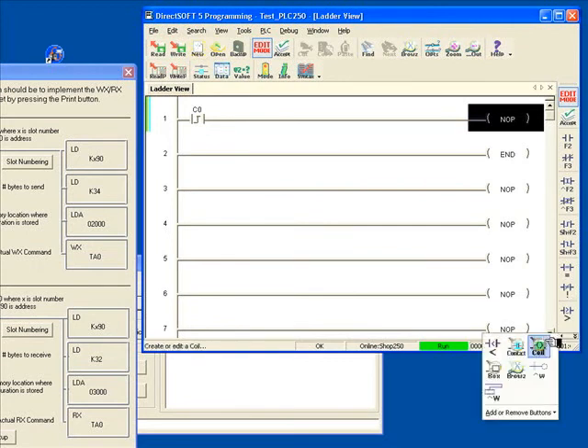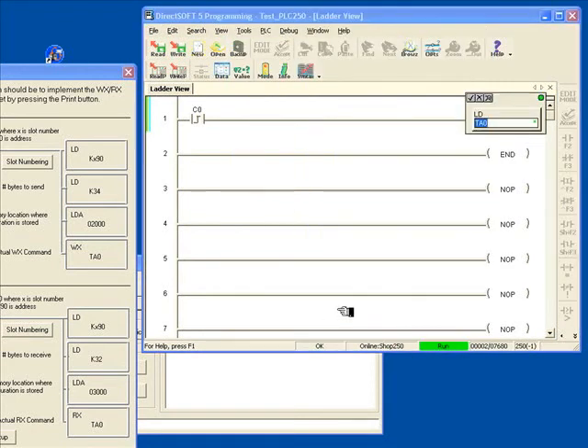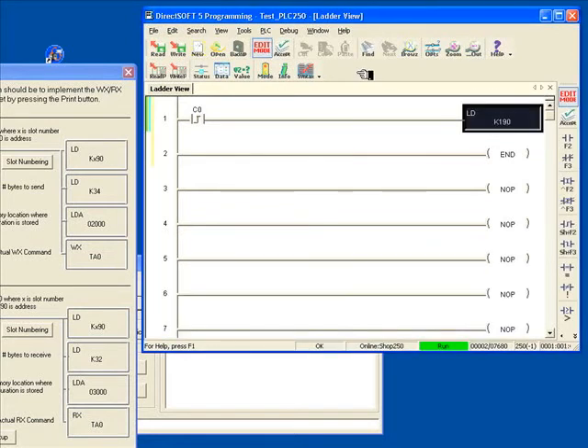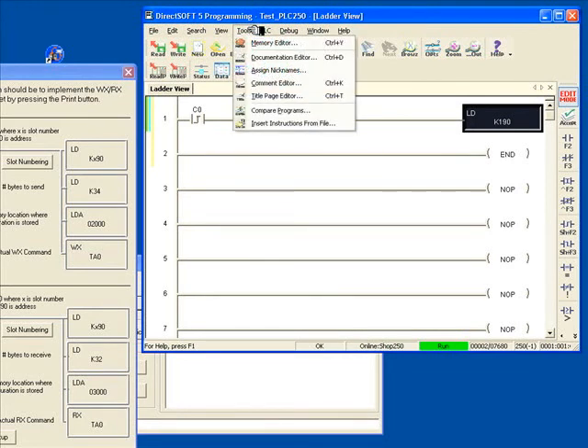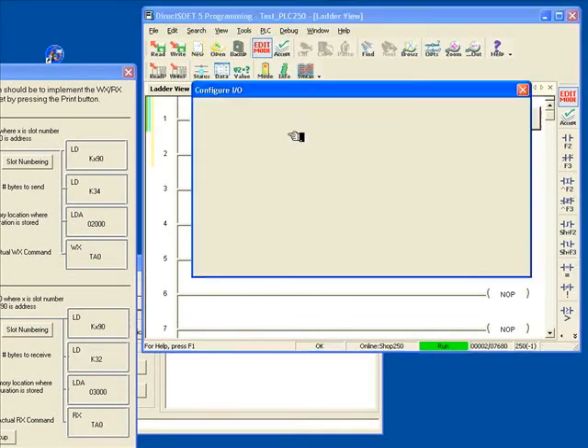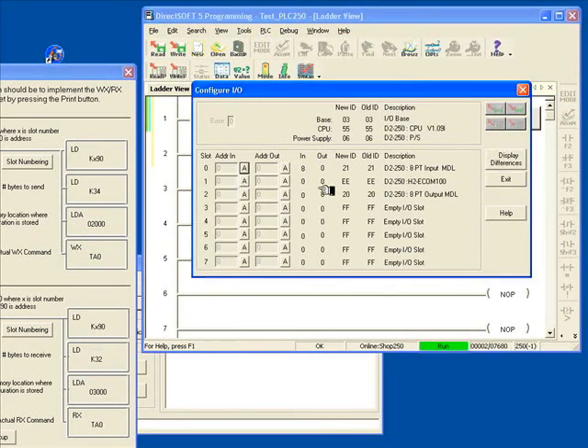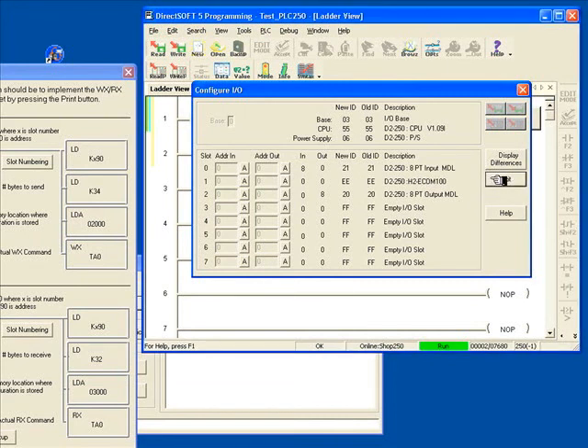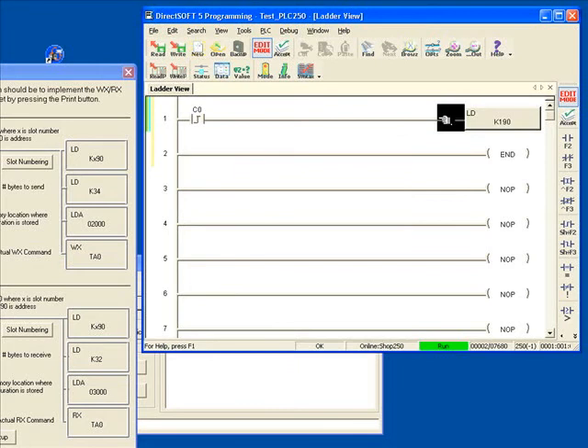And then we're going to want to do a load box, and we want to do a load. Now this is a number. This is going to be the load K, and then the first number X is going to be what slot the ECOM is in. I believe it's in slot 1, and 90 is what you always use. And to just verify what slot it's in, let's go up here to tools, I'm sorry, to PLC, and configure IO. And it'll show us, it'll populate this list, and we'll see that slot 1 is definitely the ECOM module. So we know that that first block needs to be a load K190, so it's the first slot, that's where the ECOM is at.